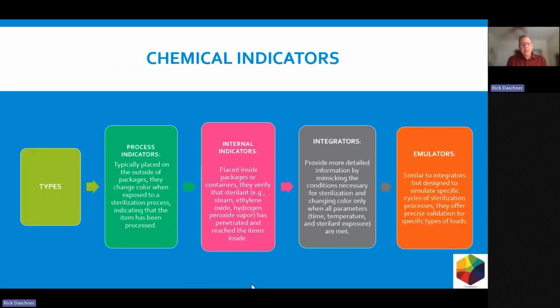So chemical indicators. First thing is, and I saw some of the questions that had come in earlier, asking what the benefits are or how chemical and biological might work together. Let's walk through what chemical indicators are used for. The biggest one is process indicators. Again, it's just to say, yes, this was run through a sterilizer, or no, it wasn't. And that's what these are for. It's not going to guarantee that everything in there is sterile, that everything worked. It just says, yes, we ran it through the sterilizer. Typically these are placed on the outside of packages. They change color when exposed to the sterilization process, indicating that the items had been processed. Again, that's what they do.